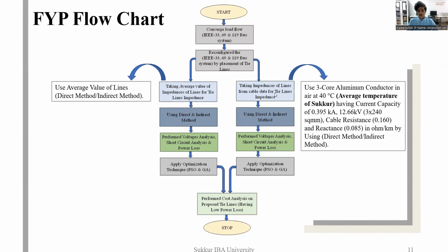Also, we take impedance of lines from cable data for tie line impedances. Here we use a 3-core aluminum conductor in air at 40 degrees centigrade, which is the average temperature, having current capacity of 0.395 kiloampere, 12.66 kV, 3 by 240 square millimeters. Cable resistance 0.160 and reactance 0.085 ohms per kilometer by using a direct method and indirect method. We have used a direct and indirect method in both cases.